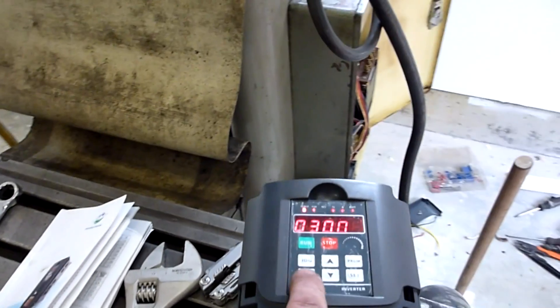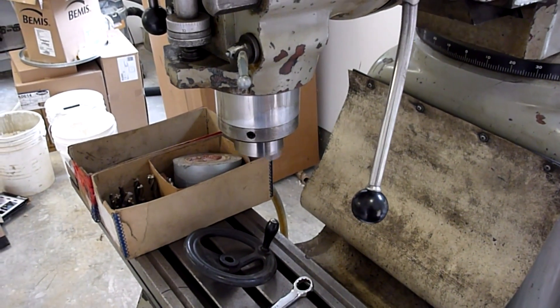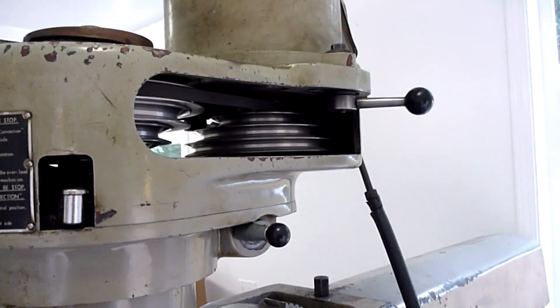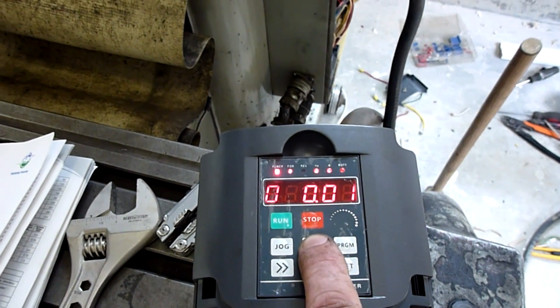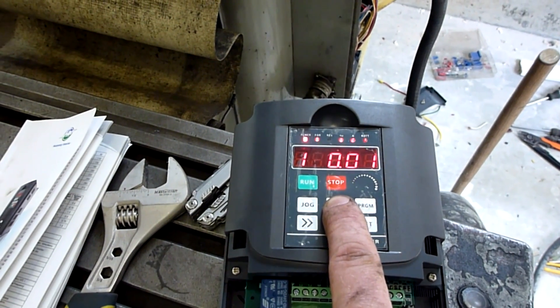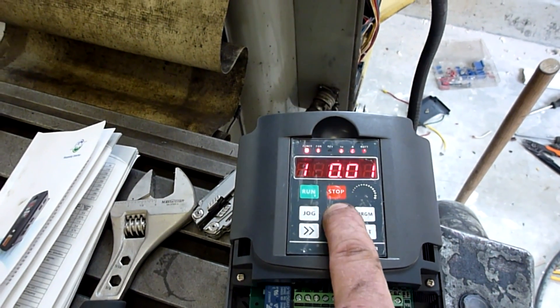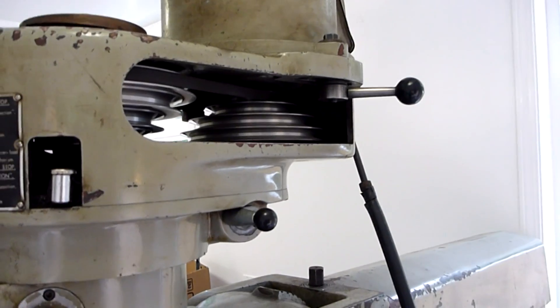Running at 30 hertz. Change that here — you can hear it winding away. If I kick that up — there is 60 hertz, that's normal running speed. There it goes: 70, 80, 90, 100, 110, 120 — it's running at 140, 150, 160 hertz. Pretty slick, huh? I'm pretty happy with that.